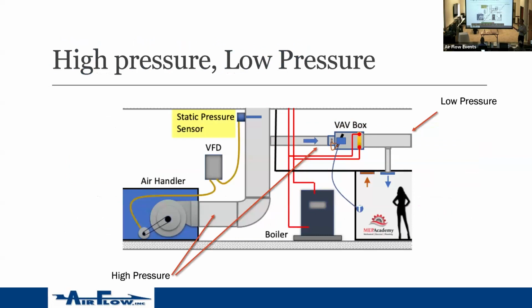Okay. Just a reminder, air handler. All right. High pressure ductwork here. We get to the VAV box, low pressure ductwork. That's the major designation. Pretty straightforward. I assume everybody knows that. If you're a younger engineer, that's the designation, high pressure and low pressure. What I'm going to show you shortly is how those two ducts look a little bit different.